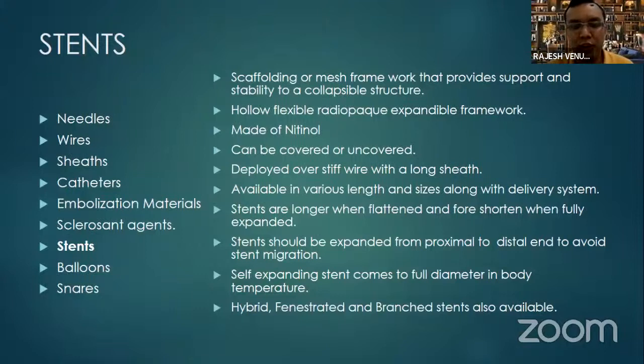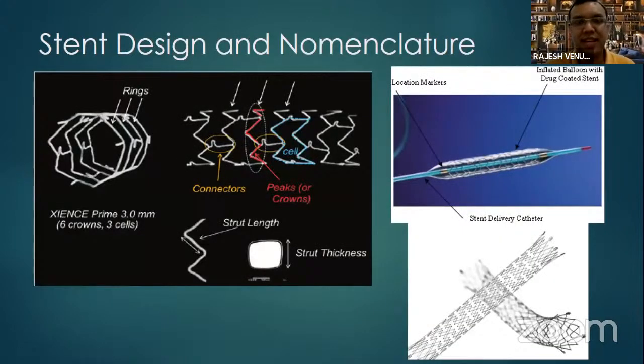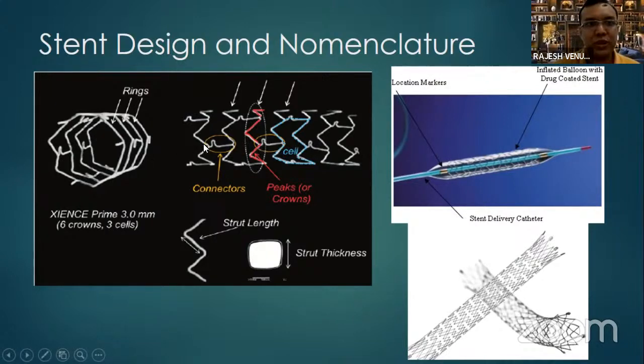A hybrid stent is one where part is covered and part is uncovered — the TIPS stent is the prototype. In TIPS, an artificial tract is created through the hepatic parenchyma from hepatic vein to portal vein; the part within the parenchyma is covered and the part within the portal vein is uncovered. Regarding stent design and nomenclature, the basic building elements are called struts — twigs arranged in a zigzag manner forming the stent framework. Struts vary in length and thickness.